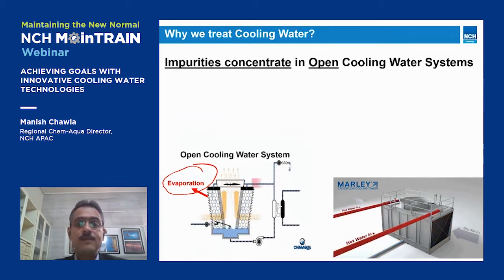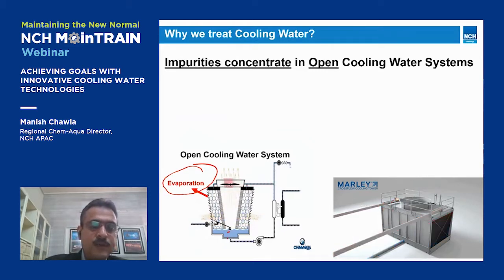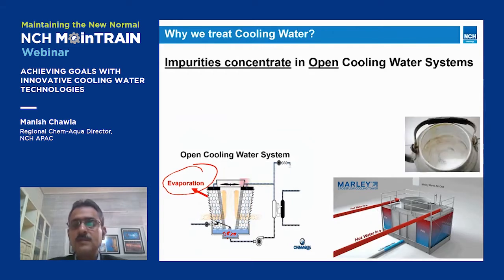But now one thing happens here. Whenever water evaporates, only pure water vapor goes into the atmosphere. No salts can go with it. So what will happen? Those salts will keep on getting concentrated in the water which is left behind. It is very similar to, say, if you put water in a kettle and evaporate it to dryness, whatever salts were in this water will tend to remain behind. So something very similar is happening in the cooling tower.